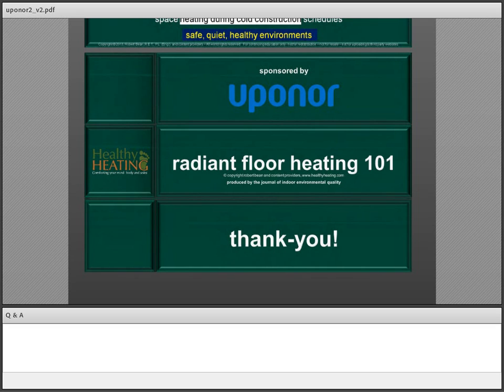You could easily see temperatures leaving the boiler at 100 degrees, 95 degrees, and a lot of that depends on tube spacing and floor covering. When you get into older or traditional buildings with really high loads, say in excess of 20 BTUs per hour per square foot, using carpeted flooring in the joist space where tubes are fastened underneath the wood floor, you can easily see water temperatures of 140 to 150 degrees. So there is no single temperature, it's always project specific. We see lower temperatures in high performance buildings using conductive masonry-type floors with tight or high density tube patterns, and that's where you get the low temperatures.